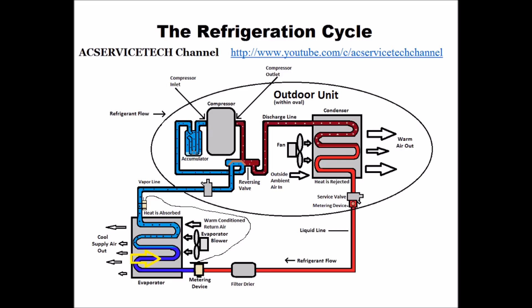It then starts to absorb heat from the house, continuing to absorb heat until it turns into a saturated state where liquid and vapor both exist. That's where it's able to store most of the heat it's absorbing from the house during that phase change from liquid to vapor. It then turns into a complete vapor and continues to absorb heat until it comes out of the evaporator coil — the indoor coil in cooling mode. The temperature increase in vapor form from where it exits the saturated state to where it exits the evaporator coil is called the superheat.